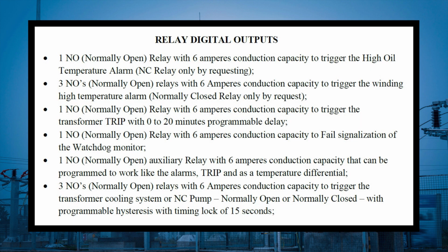The Mastertemp also has 13 relays, used for high temperature alarms of oil, high temperature of windings, ventilation groups command with programmable hysteresis, shutdowns with schedule, OLTC differential temperature alarm, monitor failure signaling, and an auxiliary relay that can also be used to indicate maintenance.